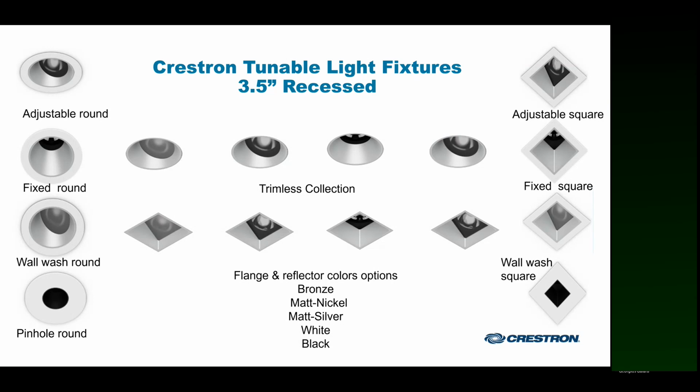Wall wash fixtures have a static 20-degree tilt and 55-degree beam spread with an additional built-in diffusion lens, giving the effect of a wider beam spread. Adjustable fixtures have a tilt capability of 0 to 40 degrees and a 360-degree rotation.